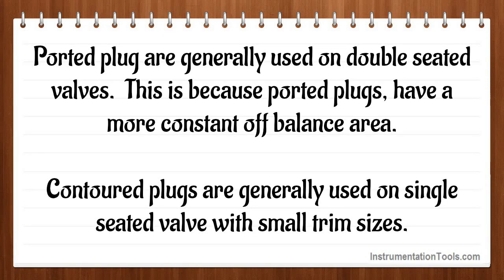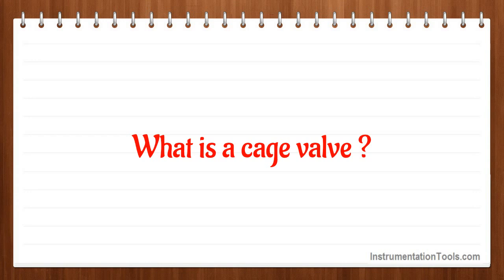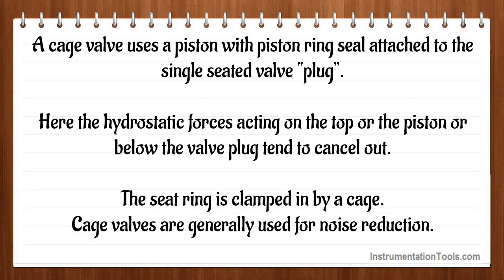What is a cage valve? A cage valve uses a piston with piston ring seal attached to the single seated valve plug. The hydrostatic forces acting on the top of the piston or below the valve plug tend to cancel out. The seat ring is clamped in by a cage. Cage valves are generally used for noise reduction.